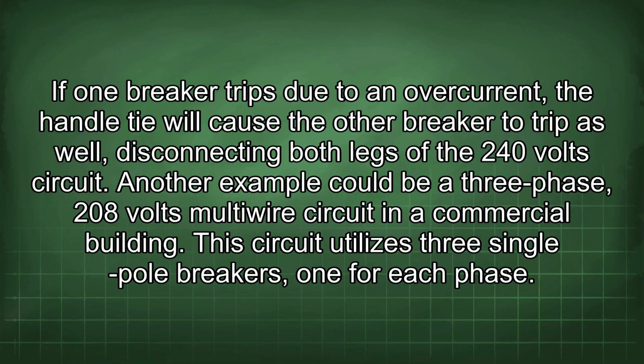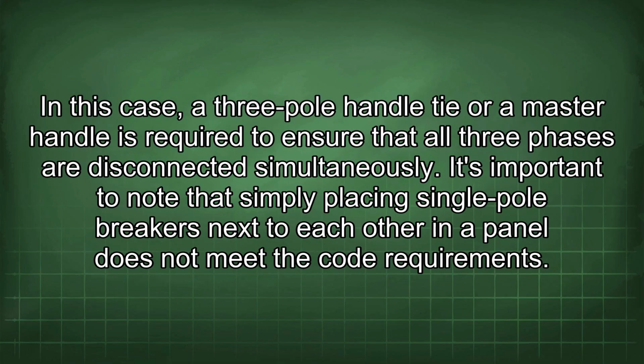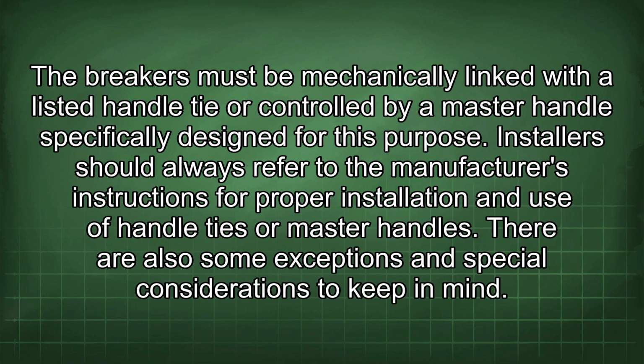Another example could be a 3-phase 208-volt multi-wire circuit in a commercial building. This circuit utilizes three single-pole breakers, one for each phase. In this case, a 3-pole handle tie or a master handle is required to ensure that all three phases are disconnected simultaneously. It's important to note that simply placing single-pole breakers next to each other in a panel does not meet the code requirements. The breakers must be mechanically linked with a listed handle tie or controlled by a master handle specifically designed for this purpose. Installers should always refer to the manufacturer's instructions for proper installation and use of handle ties or master handles.